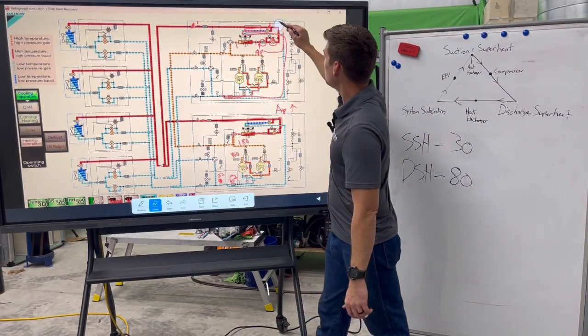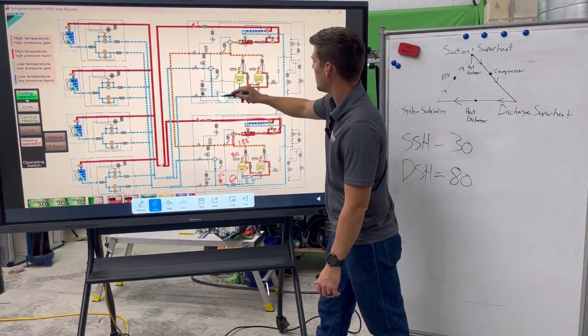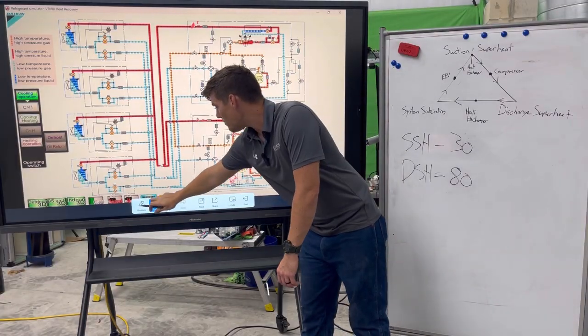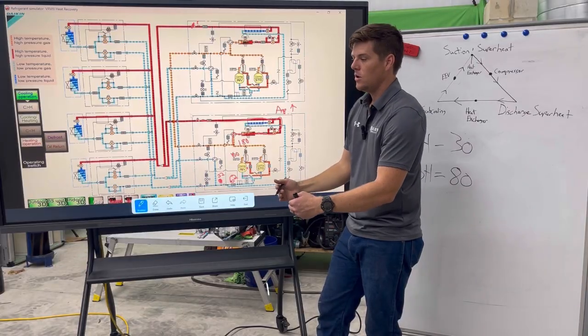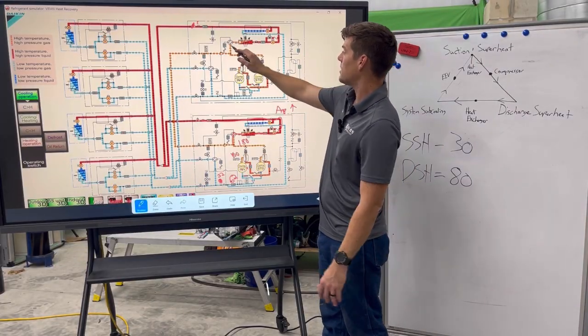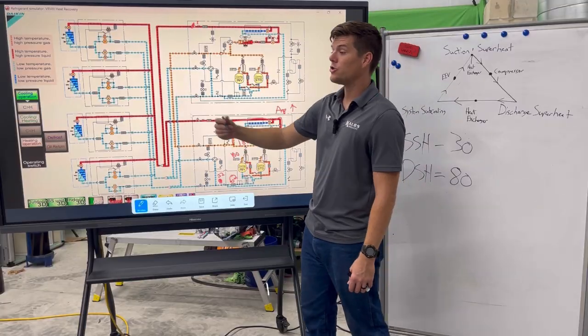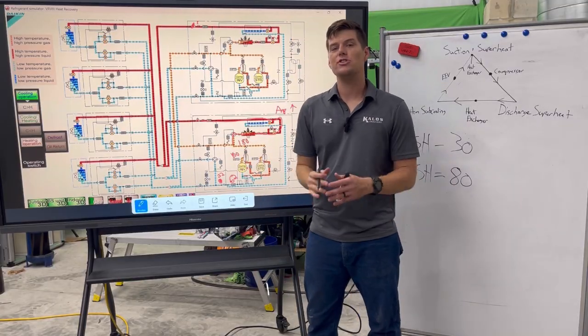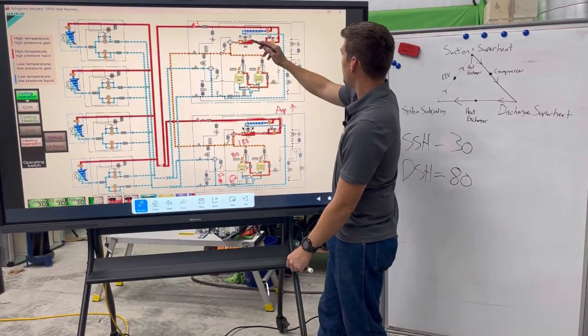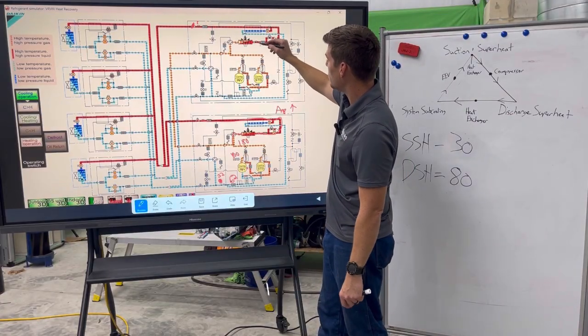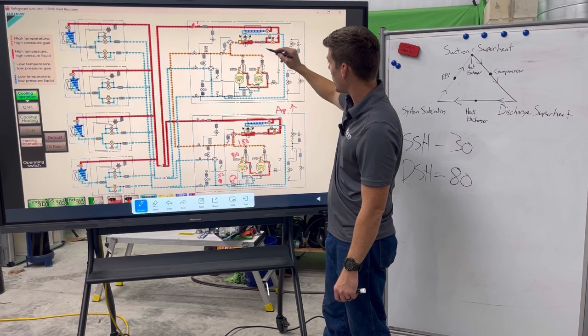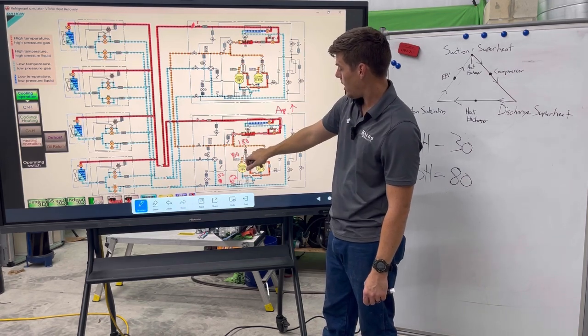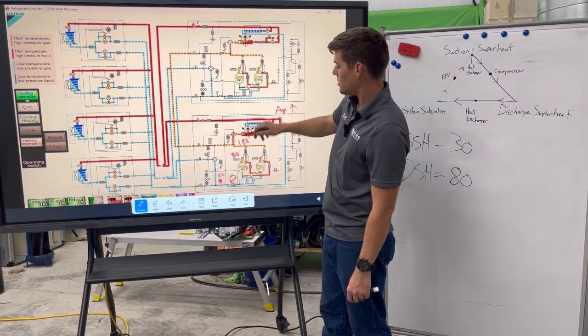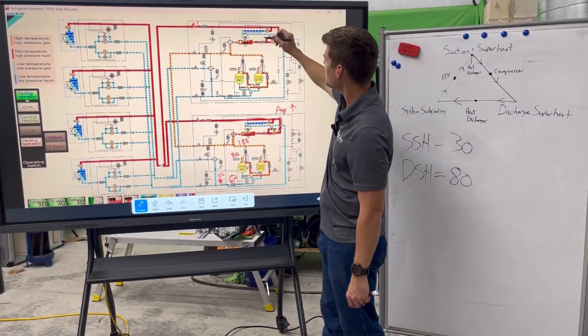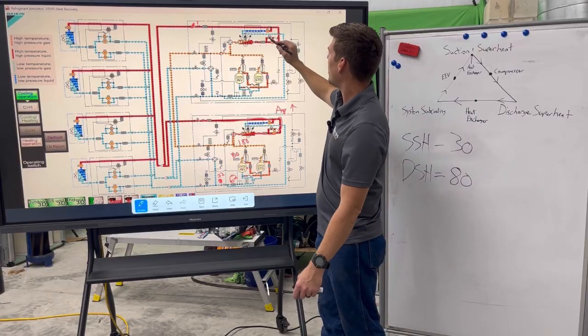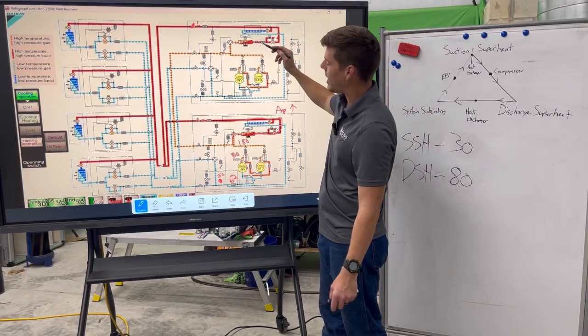We're here to talk about system subcooling. And with system subcooling, I know where I want to measure it. I want to measure it at the change of state. Well, what state change is taking place here? We have hot gas going into a heat exchanger, and out the other side it's turning to a liquid. It's rejecting heat to outside, and in the process of doing that, we are creating our subcooling. So again, we're going to come back here. We have a 100-degree liquid saturation temperature, or discharge saturation temperature, whatever you want to call it. They call it condensing temp, or TC, which is condensing temp spelled backwards.